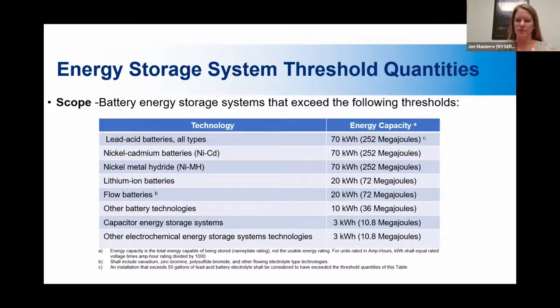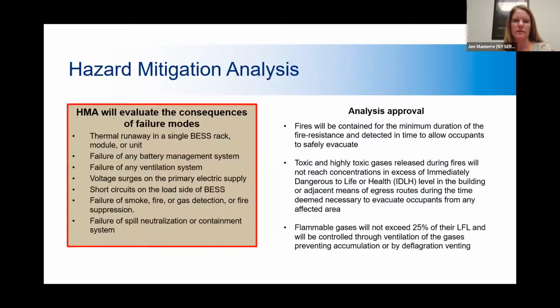So without going through all of them, for lithium ion batteries, anything over 20 kilowatt hours is going to trigger the requirements in this fire code. And that's a pretty small system. I would say residential size even. For larger systems, what we would have referred to as tier 2 in the model law, 600 kilowatt hours and above, there's going to be even more for them to do in the fire code.